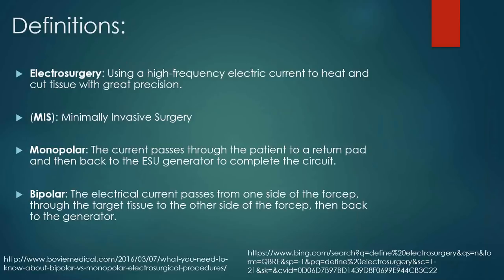Monopolar and bipolar, you hear this a lot with the instrumentation. Monopolar is basically the current that passes through the patient to a return pad and then back to the generator, the ESU generator, to complete that circuit. Bipolar is the electric current passing from one side of the forceps or instrument through the target tissue to the other side of that forceps or instrument and then back to the generator.